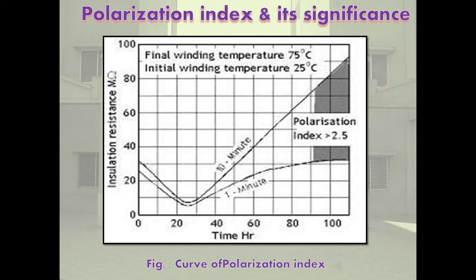Experience shows that the above methods of non-destructive testing give reliable values of the condition of insulation, moisture, surface cleanliness, and quality of insulation. It is easy to perform at site also. Typical values of insulation resistance of a power transformer in megohm: between HV and ground measurement, IR at 30 degrees is 1.34, while IR60 divided by IR15 is 1.2.